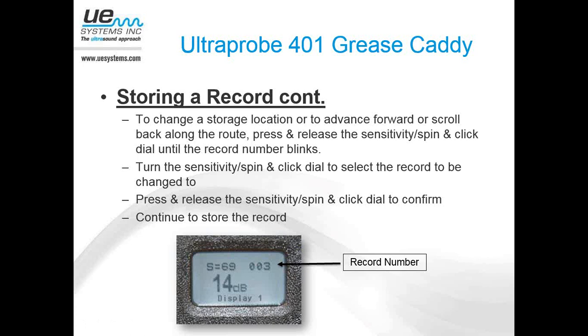And we can do the same thing if we need to scroll back and correct ourselves. So if we're halfway through the route and we realize that back at motor 2 we took the readings in the wrong location, or maybe we even took the readings on the wrong asset, we can scroll back to those points and then go back and correct ourselves. So it'll overwrite that bad data with the good data.